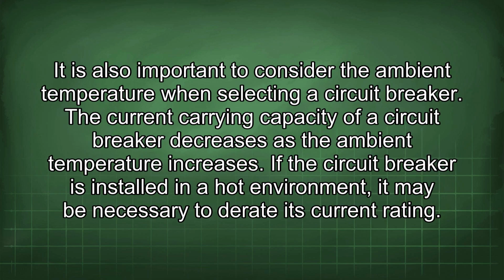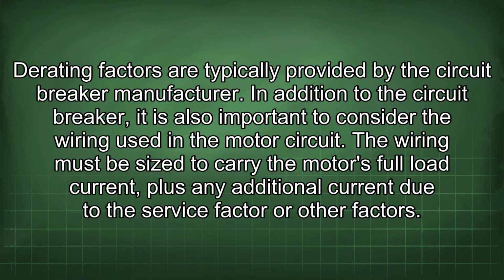It is also important to consider the ambient temperature when selecting a circuit breaker. The current carrying capacity of a circuit breaker decreases as the ambient temperature increases. If the circuit breaker is installed in a hot environment, it may be necessary to derate its current rating. Derating factors are typically provided by the circuit breaker manufacturer.